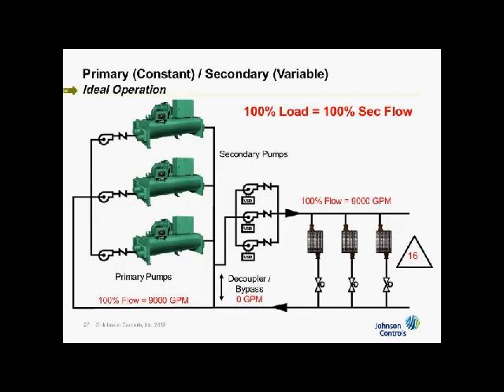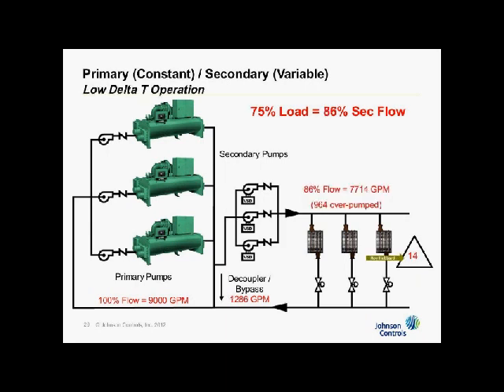Under ideal operation, as you saw before, 100% load is equal to 100% flow, and delta T is 16 degrees. Okay? Now, when I'm at 75% under ideal operation, 75% load means 75% flow. But what happens when I have low delta T? Meaning I don't have 16 anymore, I've got 14. Now 75% load is equal to 86% secondary flow. So I'm now over pumping.